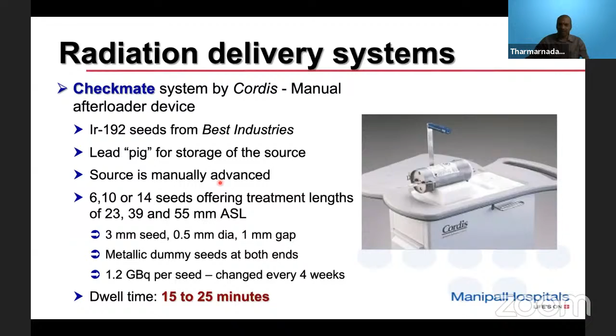The source is manually advanced. You can see here that the source is manually advanced by means of this crank. Just like a crank wheel, you have to rotate it in order to push the source inside the patient and also retract it back. Either a 6 seed, 10 seed, or 14 seed assembly was used in this device, offering treatment lengths of either 23 mm, 39 mm, or 55 mm active source length.